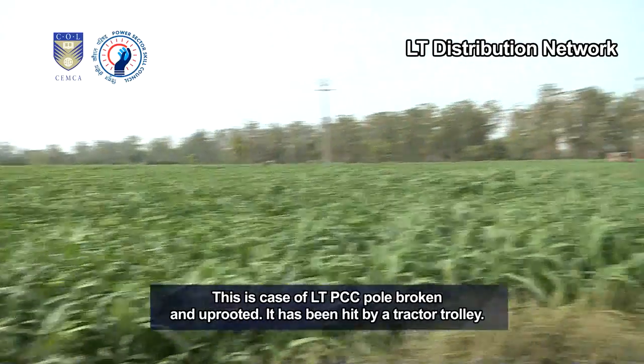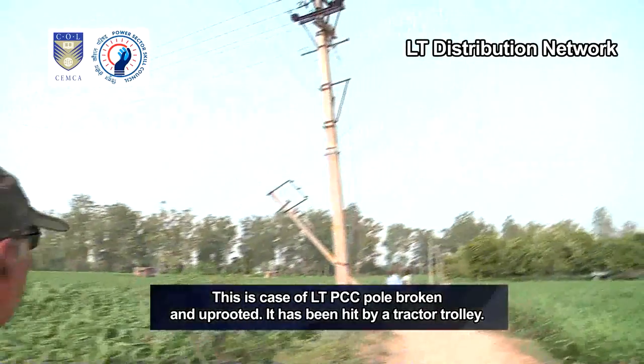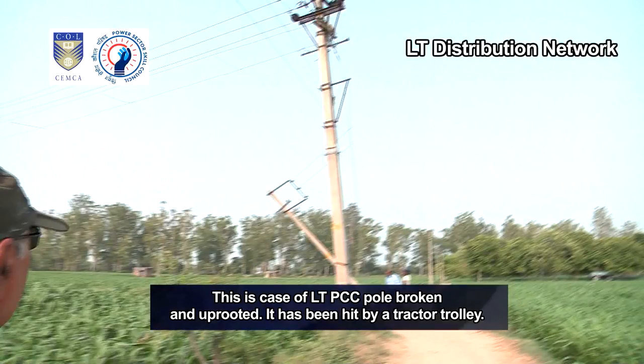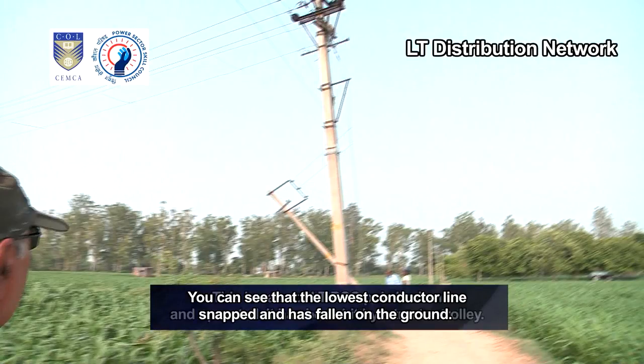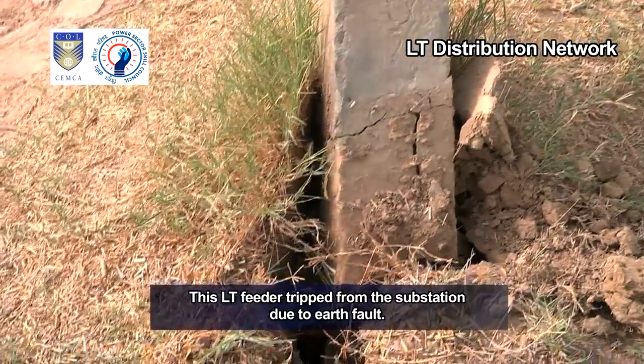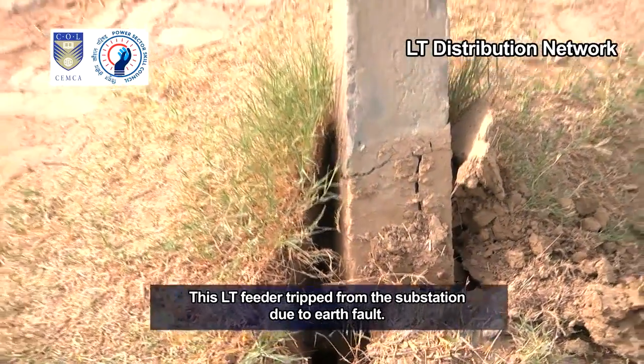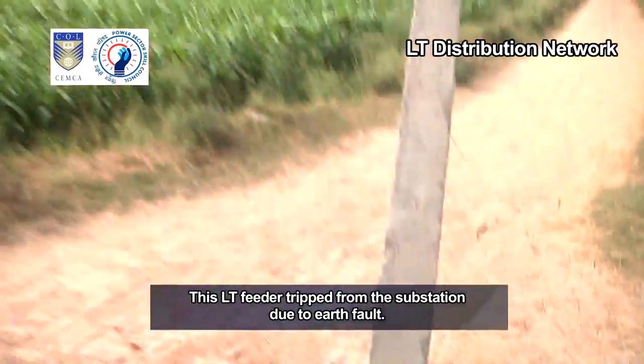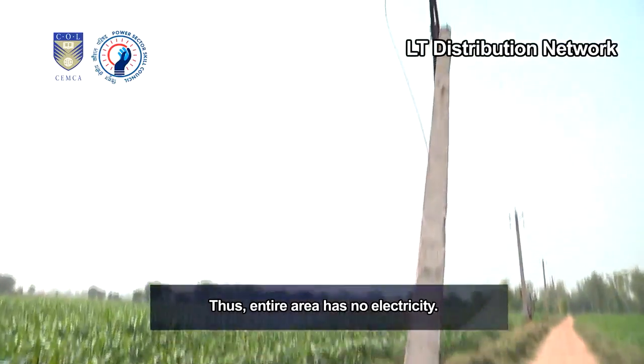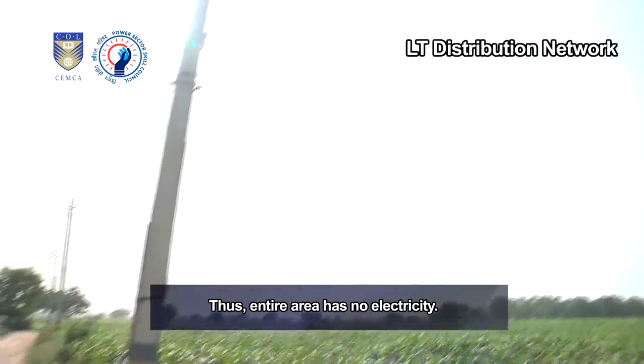This is a case of an LT-PCC pole broken and uprooted. It has been hit by a tractor trolley. You can see that the lowest conductor line snapped and has fallen on the ground. This LT feeder tripped from the substation due to an earth fault. Thus, the entire area has no electricity.